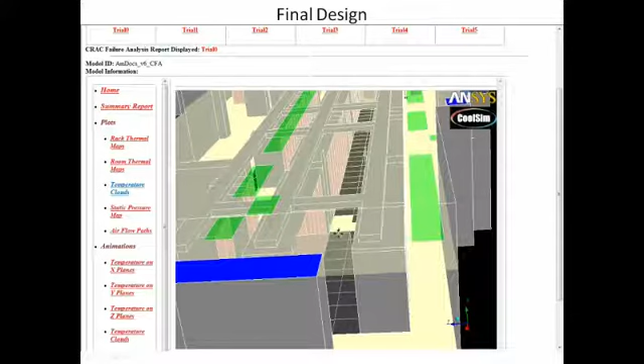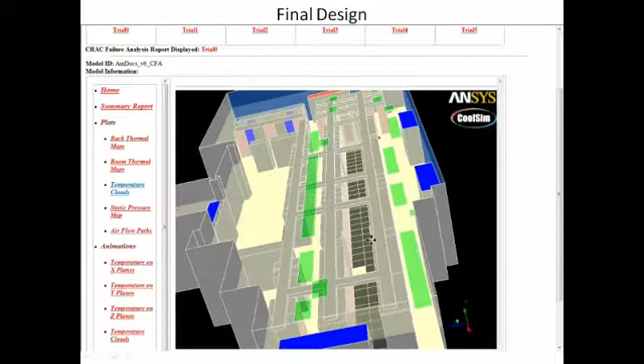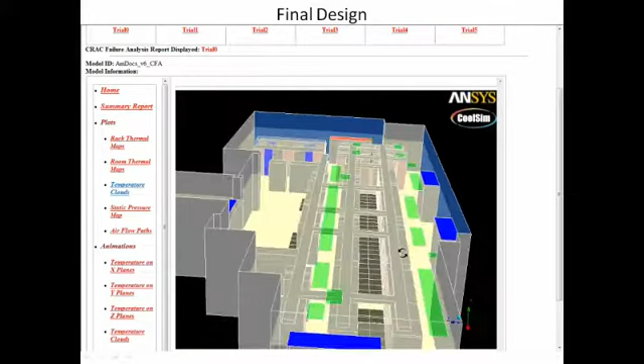Right, so to start that, you put curtains on the end caps. And I see here you've got some baffles in the center, some sealing between these. Exactly. There's certainly a lot of fire protection work that would have to be done to create a fully encapsulated cold aisle in this case. So to make a small incremental improvement, the customer opted to just add some curtains on the ends as well as in the gaps in the row.